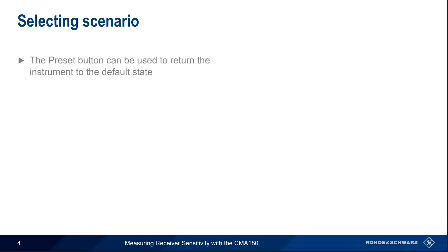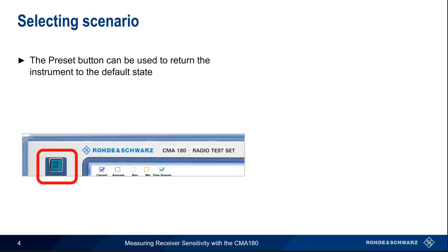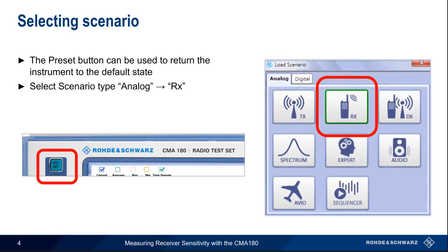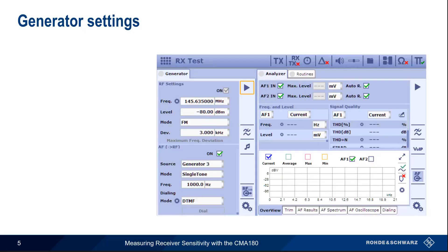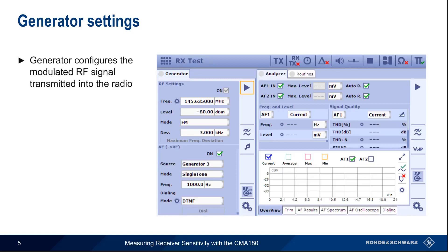If needed, the green preset button on the front of the CMA-180 can be used to return the instrument to its default state. Sensitivity is a receiver measurement, so we start by selecting Rx from the list of analog scenarios. For our sensitivity test, the CMA-180 needs to generate a modulated RF carrier that is input into the radio under test, and this is configured using the Generator tab.